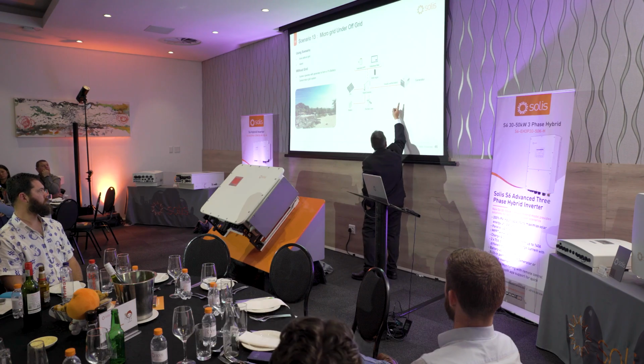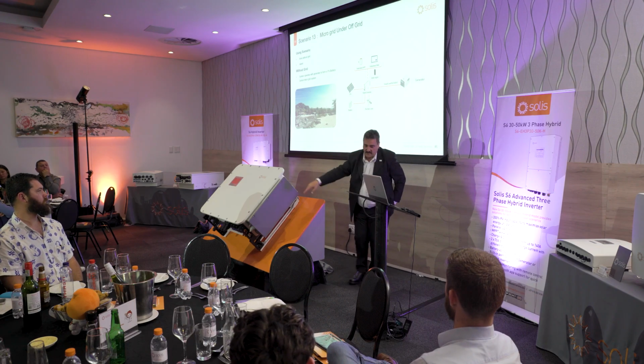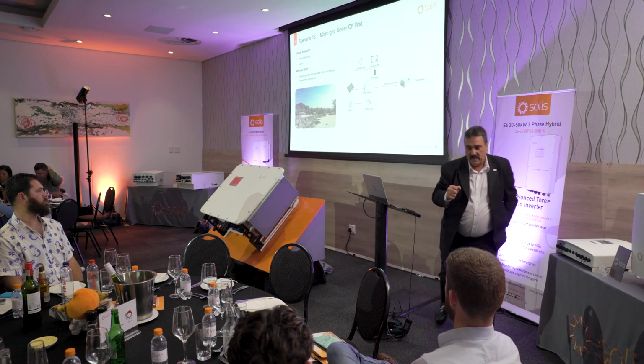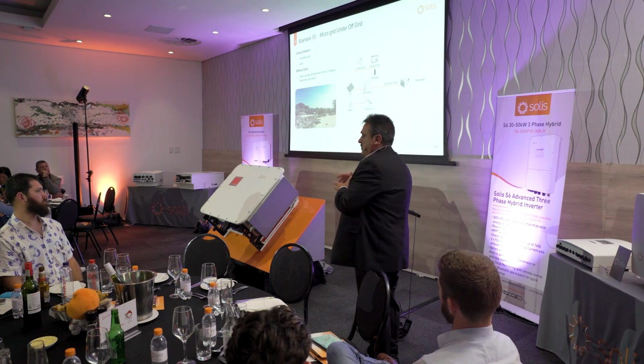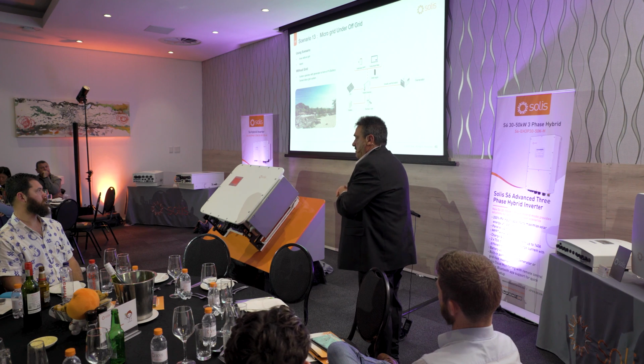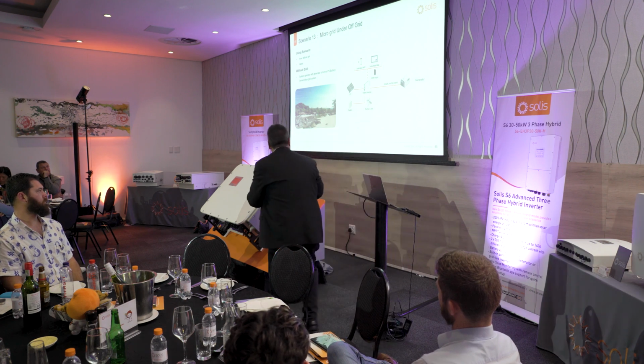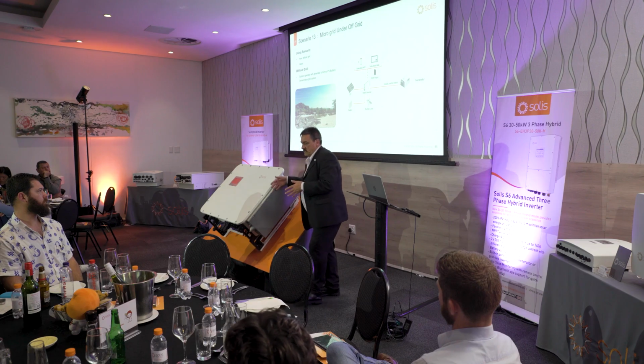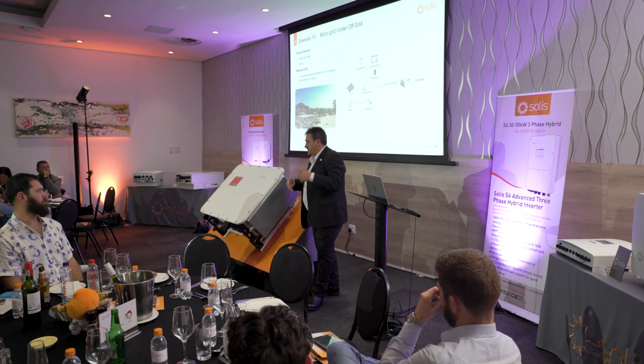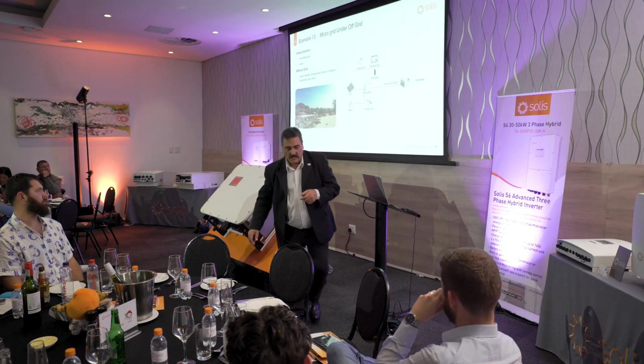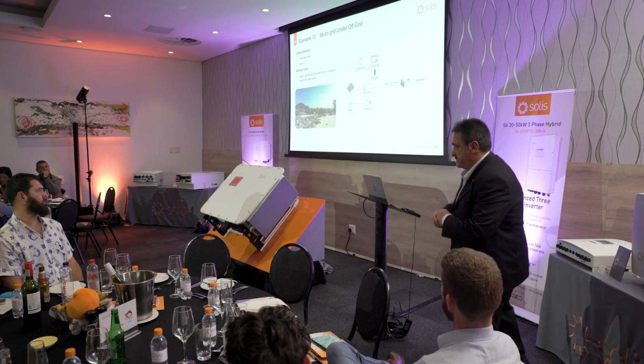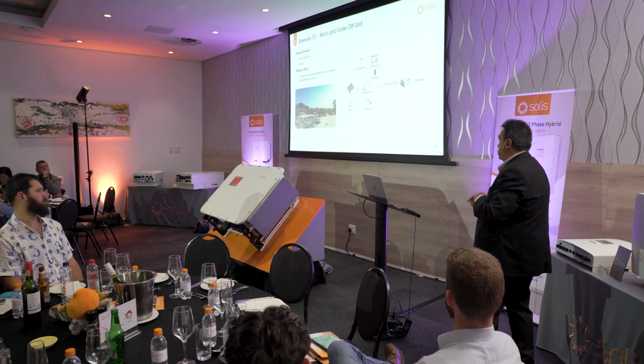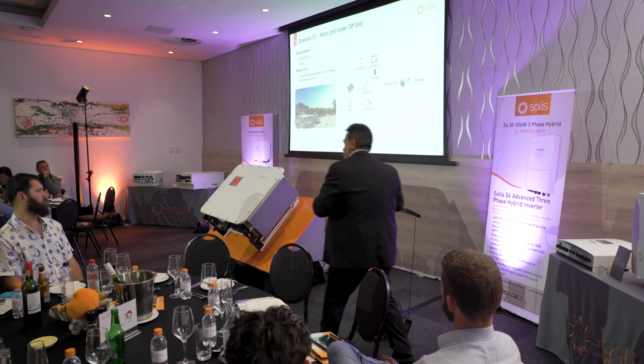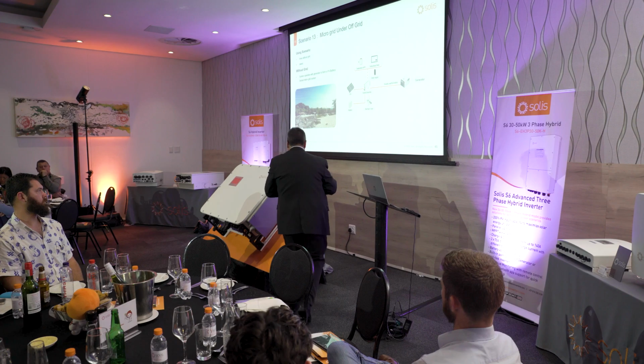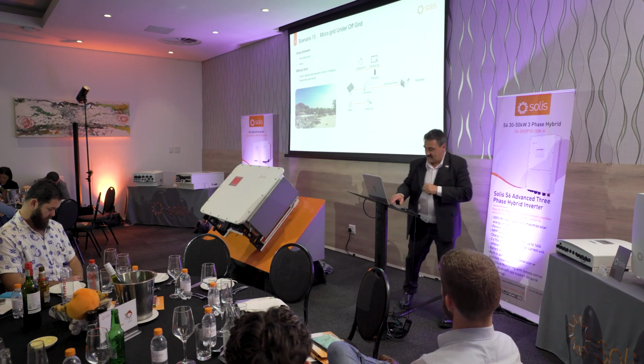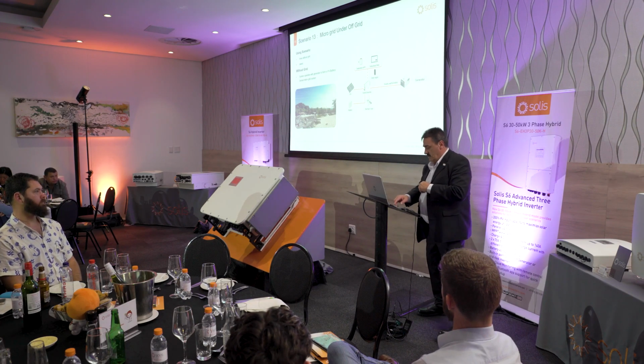There's a signal that you need to just get from the generator. It comes in here, it's normally like a 5-volt digital signal. And once the inverter receives that, it will know that the generator is now running. Okay? Because also the thing is, once the generator runs, this turns into wanting to export power to the grid because it thinks it's grid. Okay? So we can't allow that to happen. You can't export back onto the grid. So we have a bunch of settings in there for you that allow you to set spinning reserve of the generator and all those wonderful functions to protect the generator. It is, again, exactly the same as in any one of these other things.